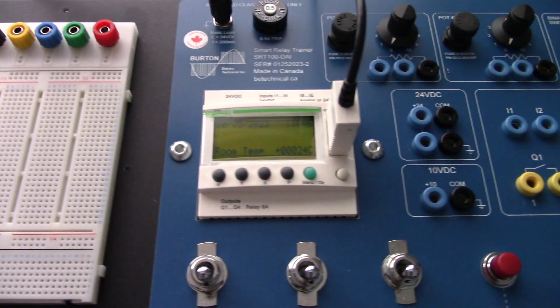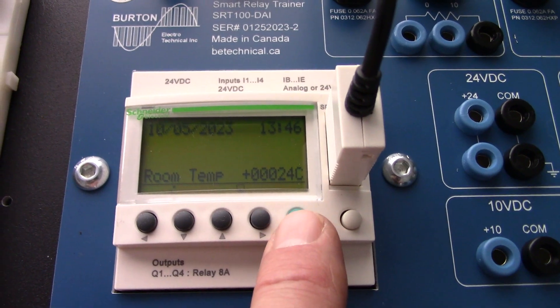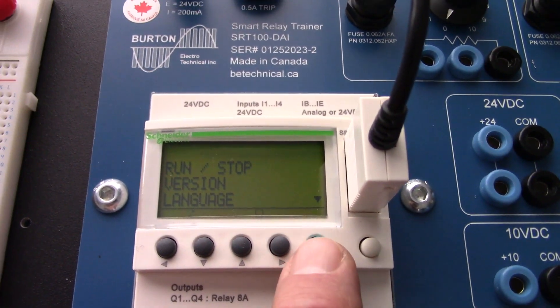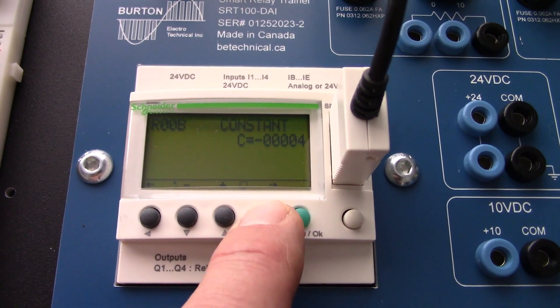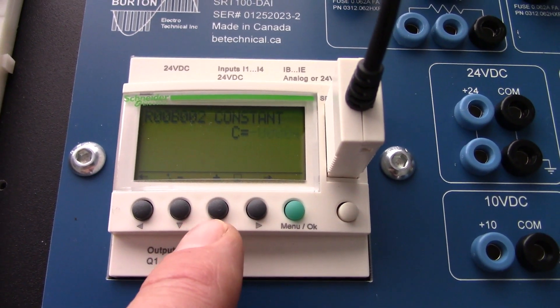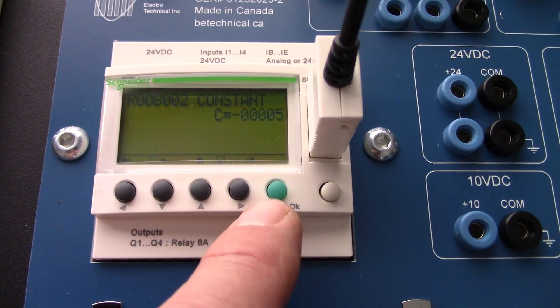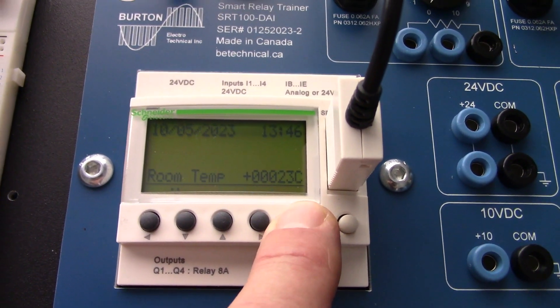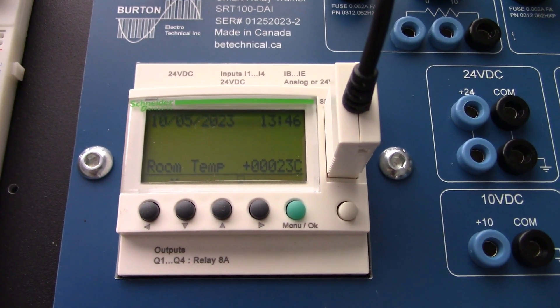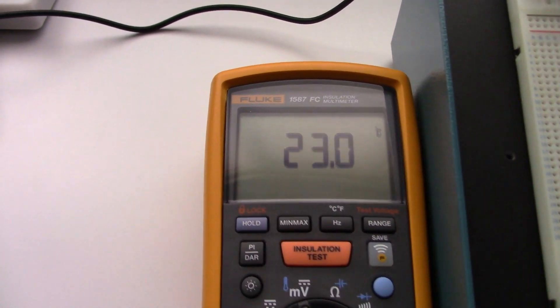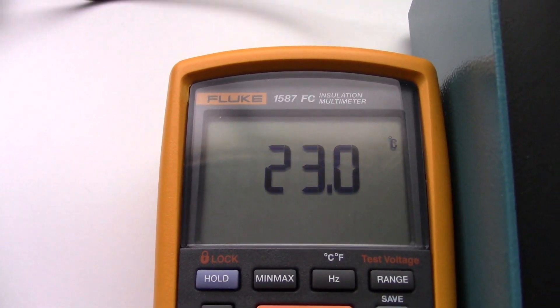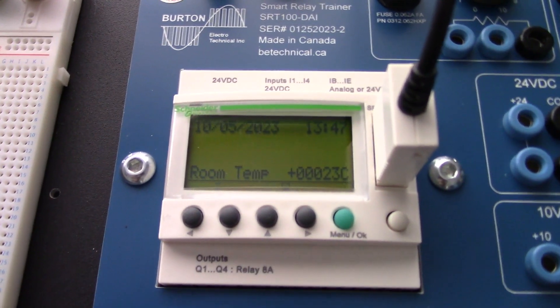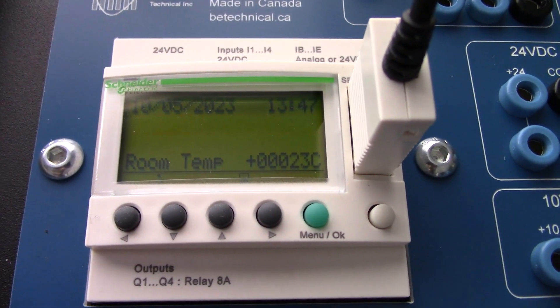We'll do it again. Menu button. Parameters. Enter. Then we scroll over. Constant. We'll take it down one more. Click OK. Click yes. Now it says 23. And our $900 meter, that's Canadian dollars, says 23. So we calibrated by using that little addition block. Basically, we're just using an offset to calibrate it, which will work great for room temperature.